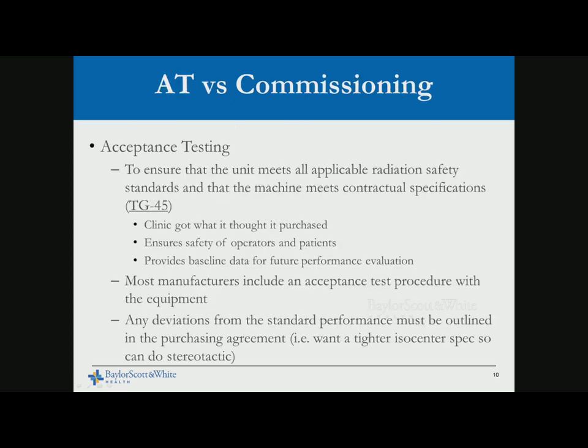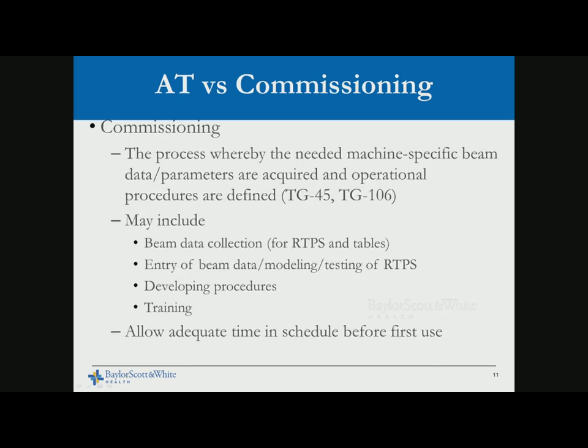Specialized treatment systems like CyberKnife or tomotherapy come commissioned — we just do the validation. But for conventional LINACs, acceptance testing and commissioning are two separate pieces. Acceptance testing ensures the clinic got what it purchased, ensures safety of operator and patient, and provides a baseline for future performance evaluation — this is currently a shortfall in how acceptance testing is performed. Commissioning prepares your LINAC for clinical use: beam data collection, procedure development, and staff training.